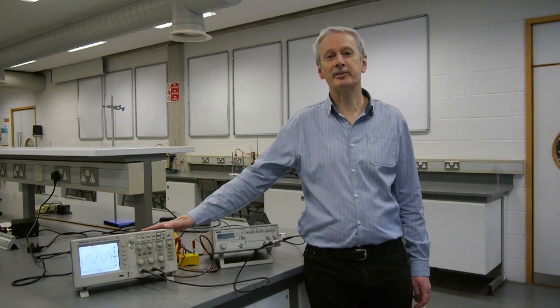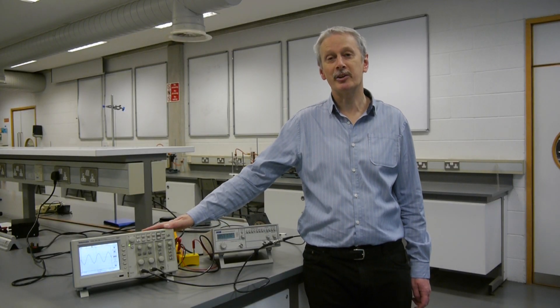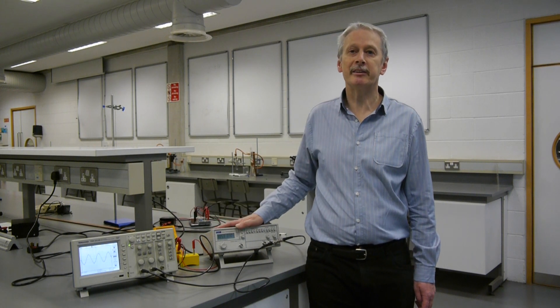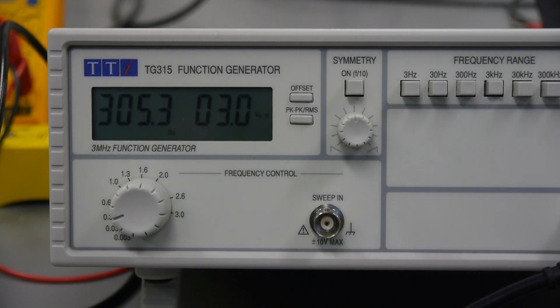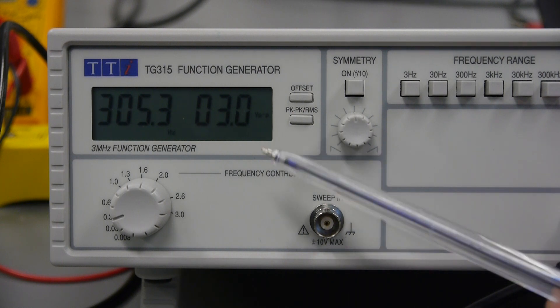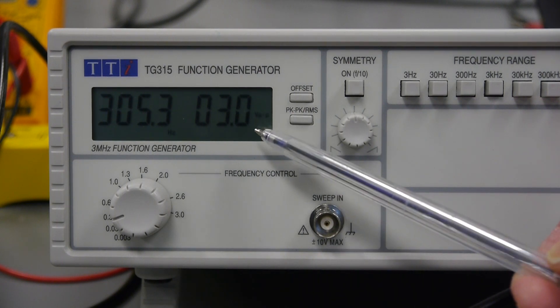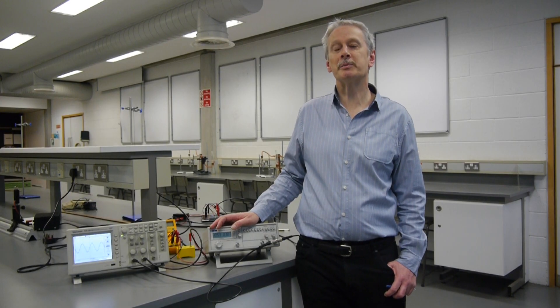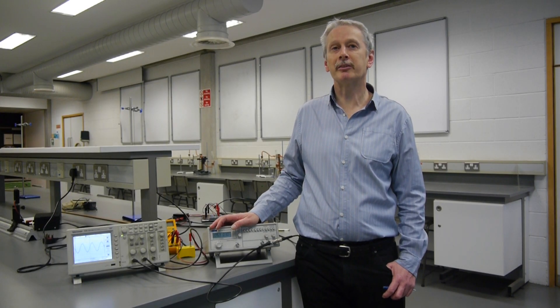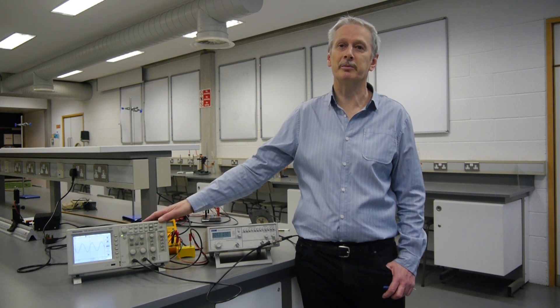Now we saw that our oscilloscope measures the peak-to-peak value as 30 volts, but our signal generator also tells us the peak-to-peak value it's putting out. But looking at the display, it's telling us it's just putting out 3 volts peak-to-peak, not the 30 volts the oscilloscope is telling us. The reason for the difference between the two readings is that we've not correctly set one of the side menu buttons on the oscilloscope.